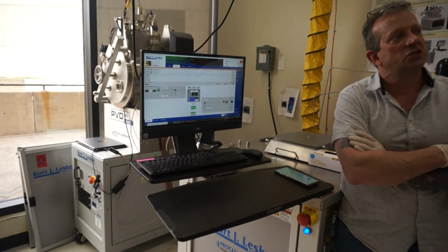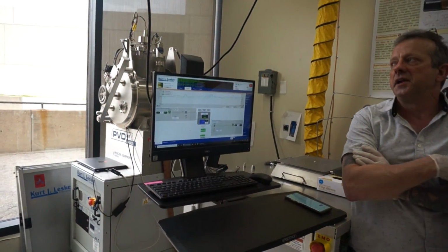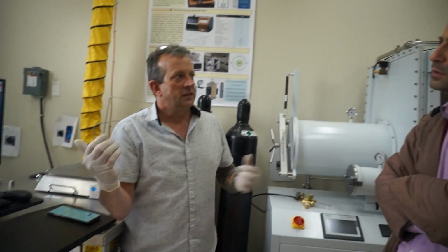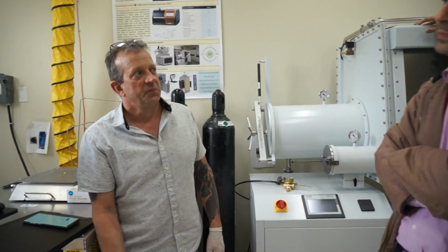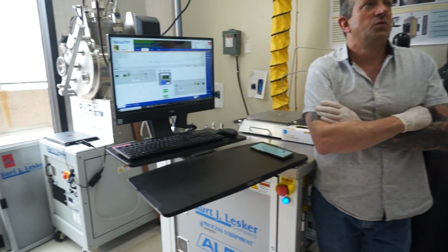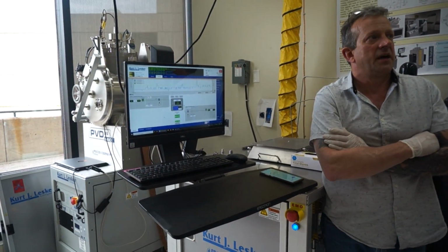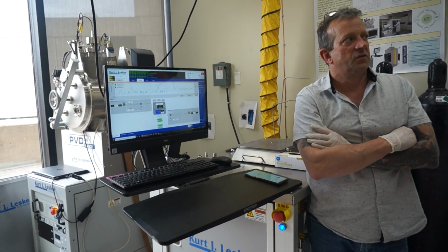So you can't go with just 5 cycles. So you can't put too much. In the PVD system, if you're depositing too much, it's going somewhere. In the ALD, you're not reacting, so you're not getting any more build. It's either reacting in the foreline or all the chemistry is going to the pump. So as you run it, especially if you're running the same recipe all the time, you'll know how many cycles you can get. You get a feel for it.